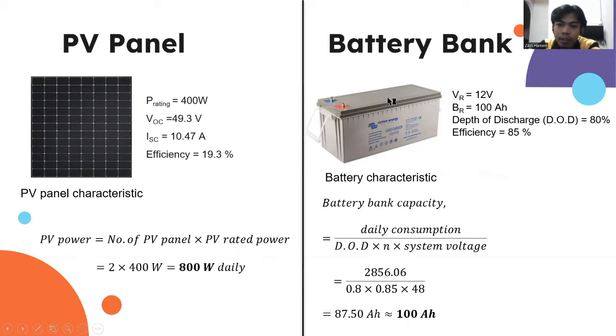Next is the battery bank. For the battery bank capacity, we use this formula to calculate. The daily consumption is the daily house usage, which is 2,856.06 watts. We use this for the calculation and we get 87.50 ampere hour. So the suitable battery bank capacity is 100 ampere hour.